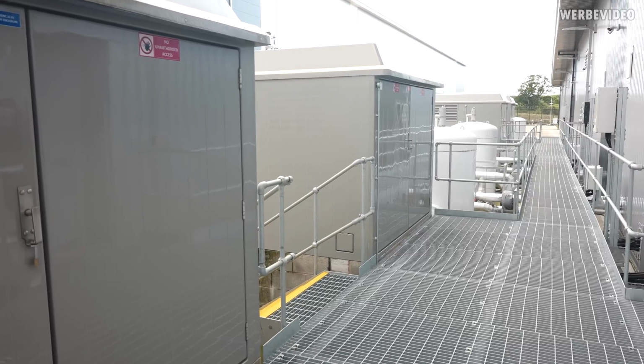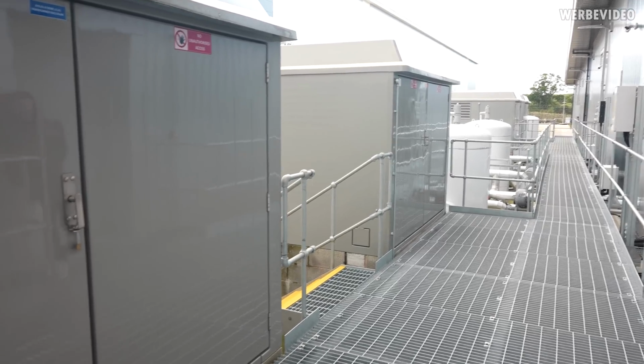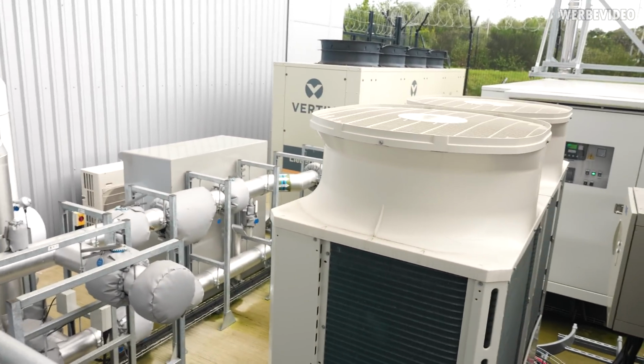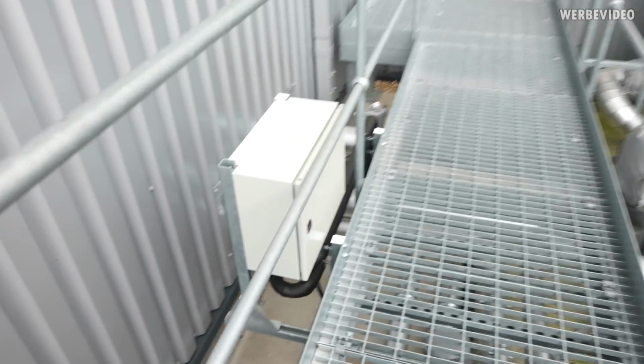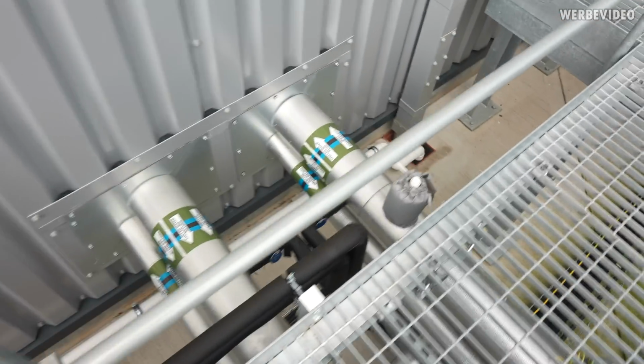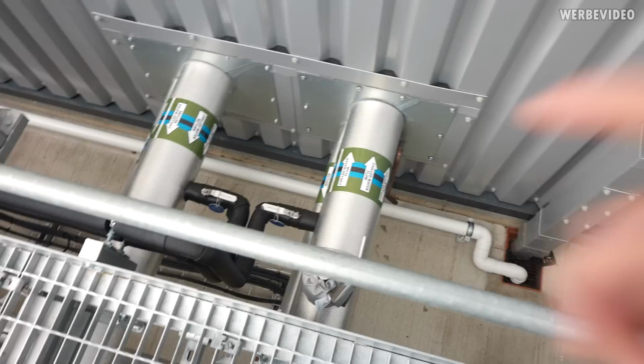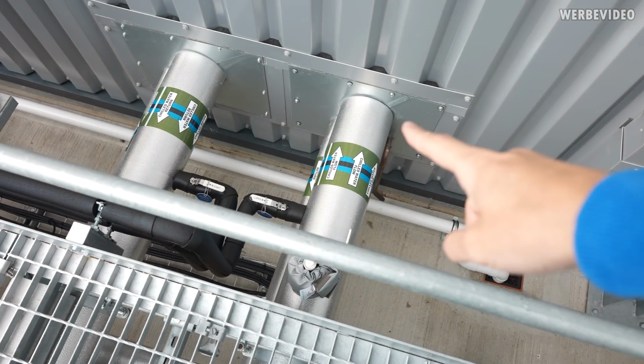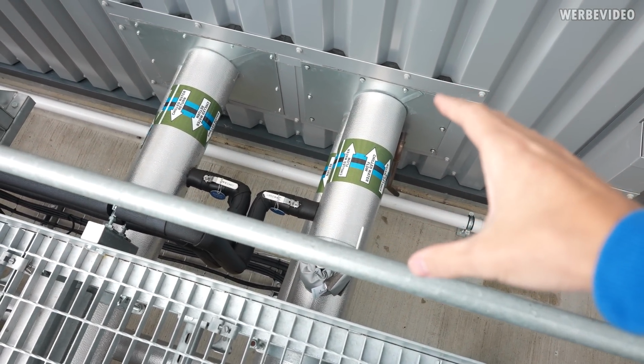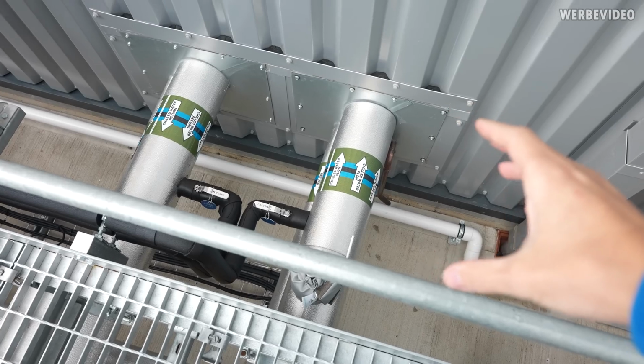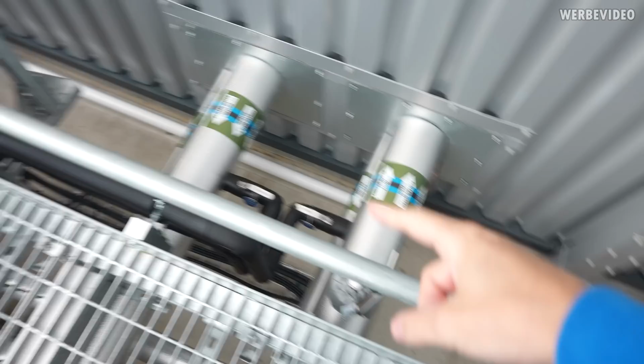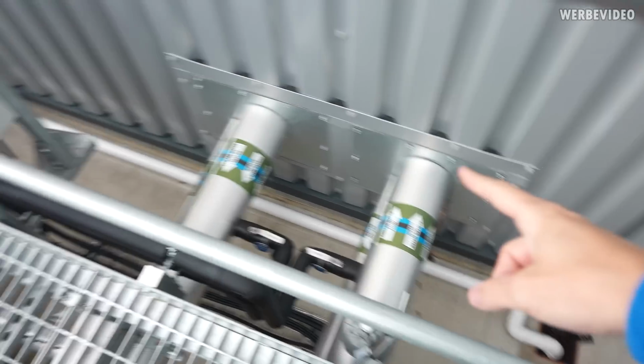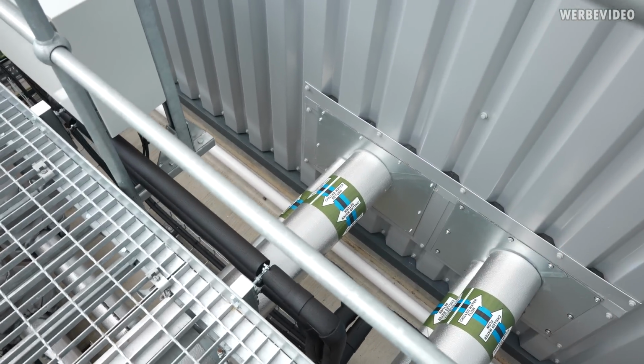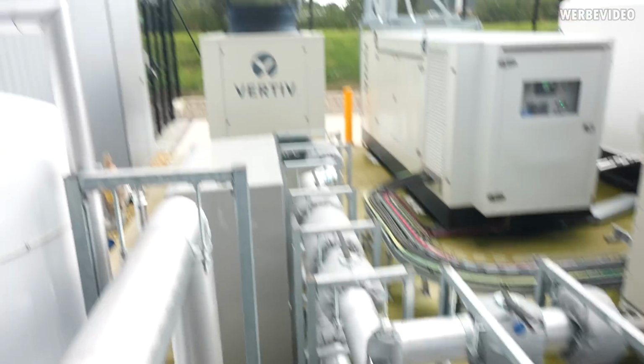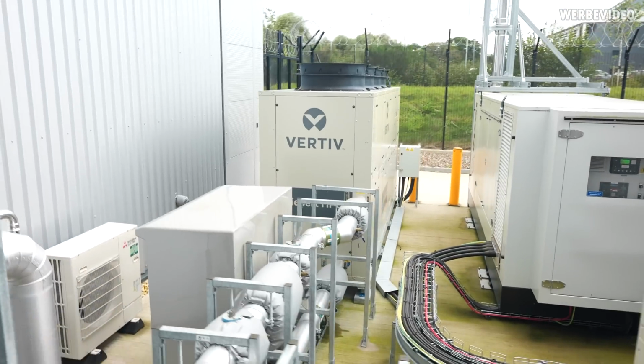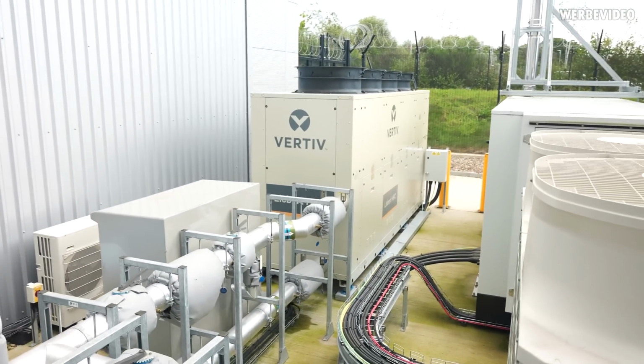We are now back outside, but on a different side. This is stuff we haven't seen yet, but I wanted to show that it actually exists. Down here we have the pipes, the cold water pipes. That's where the cool water accesses the data center, flows through those chambers and the heat exchanger, and comes back slightly warmer. It enters here at about 20 degrees Celsius and comes back out at maybe 23 degrees Celsius.